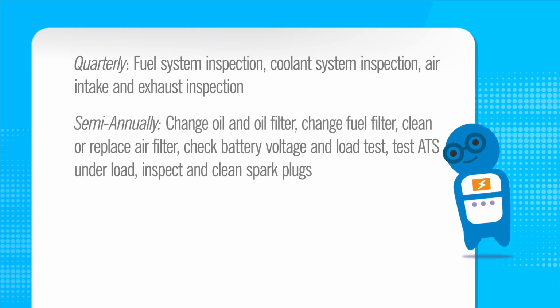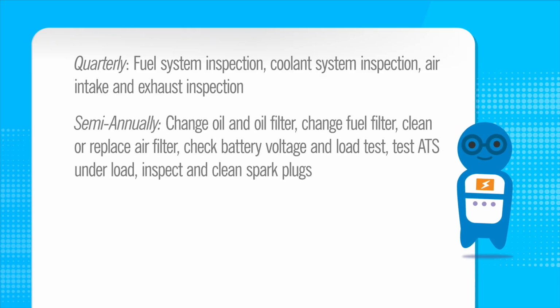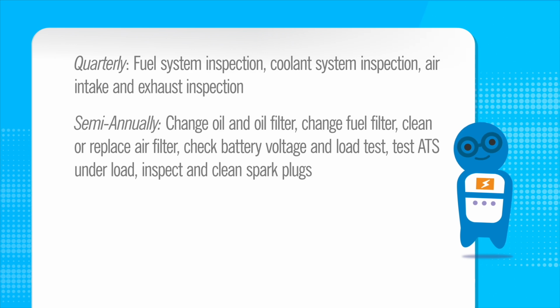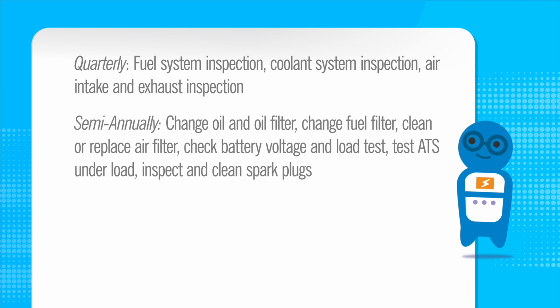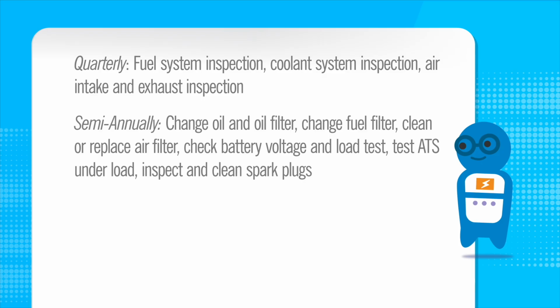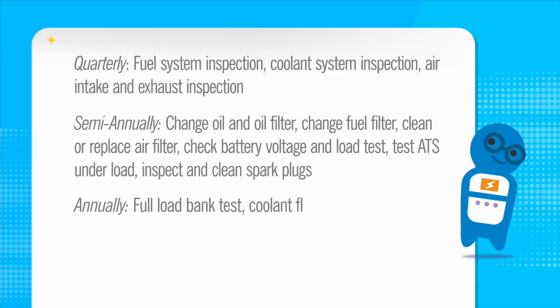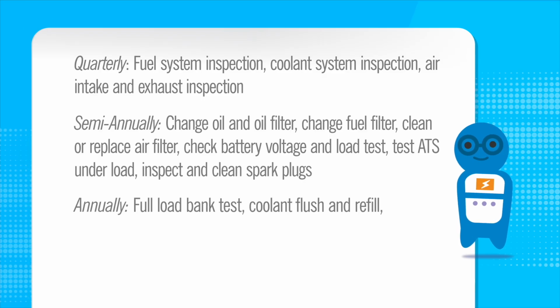Semi-annually: change oil and oil filter, change fuel filter, clean or replace air filter, check battery voltage and load test, test ATS under load, inspect and clean spark plugs. Annually: full load bank test, coolant flush and refill.